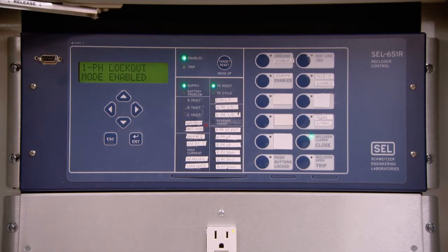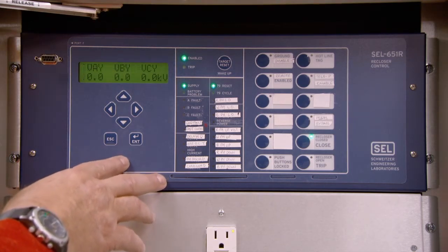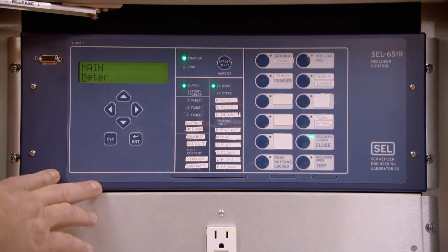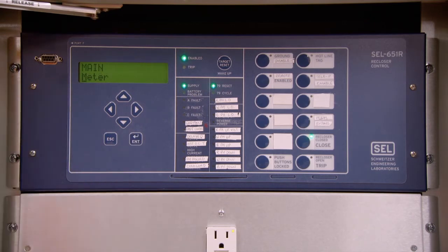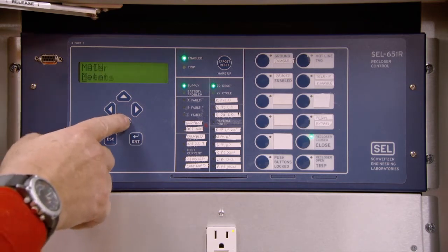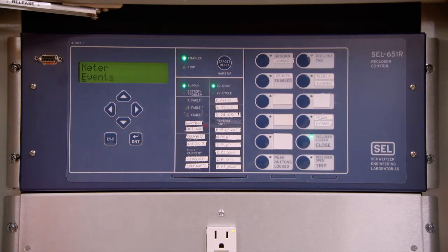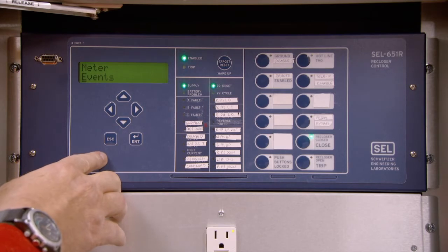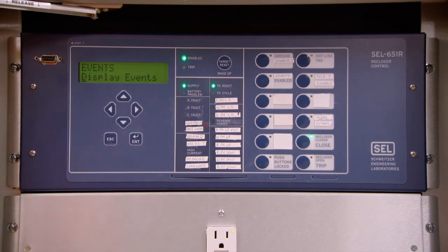The next menu in the scrolling screen after Meter is Events. To arrive at this menu, one must press the Enter button upon seeing the main meter screen. This will stop the screen from scrolling and remain at the Meter menu. To move to Events, press the down arrow. Events will be populated by anything that actually trips the recloser open. Pressing Enter will show Display Events.